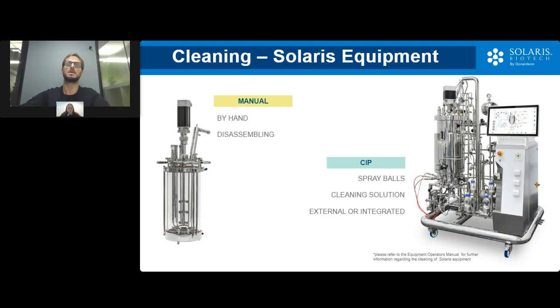So how is it possible to clean a bioreactor? For smaller scale vessels, it is possible to clean the equipment by hand, of course, opening the head and accessing all the components in contact with the process. This is acceptable and easy to manage for benchtop units, as they are generally light and all the parts are easily reachable. Regarding glass and stainless steel solutions, they have been designed to grant fast disassembling. Of course, when it comes to pilot or manufacturing scale, the hand cleaning process becomes a hurdle, physically speaking, and a limiting factor to a fast turnaround time.